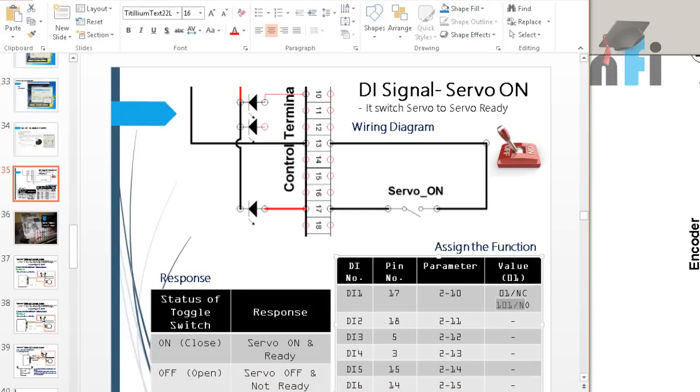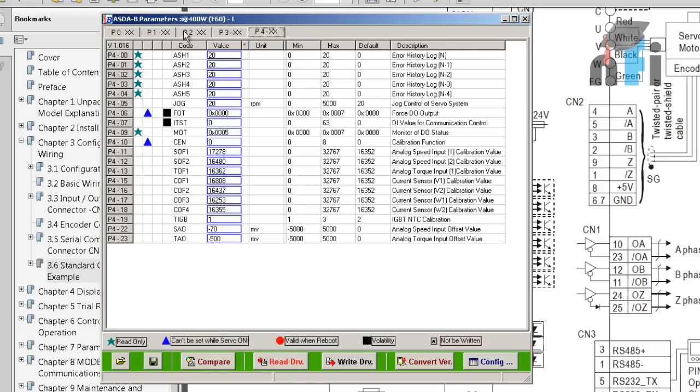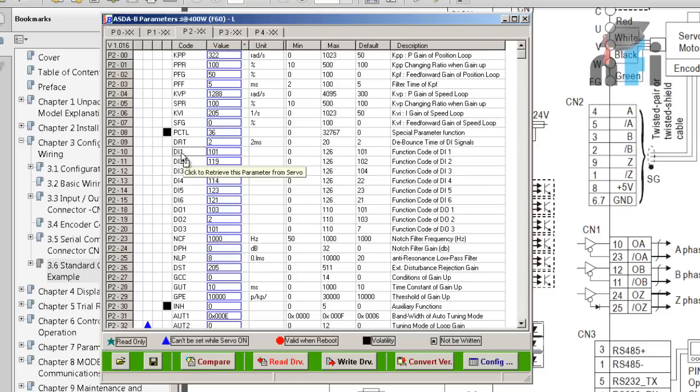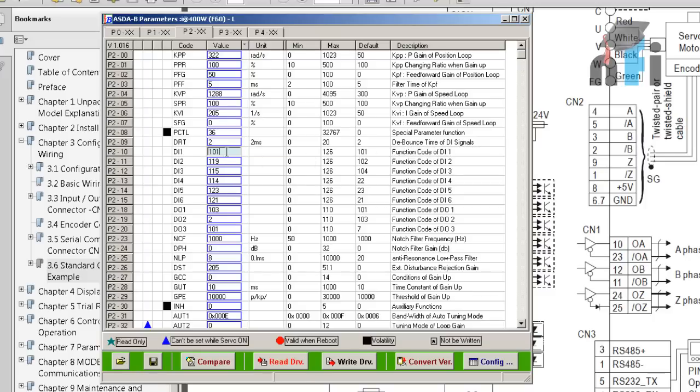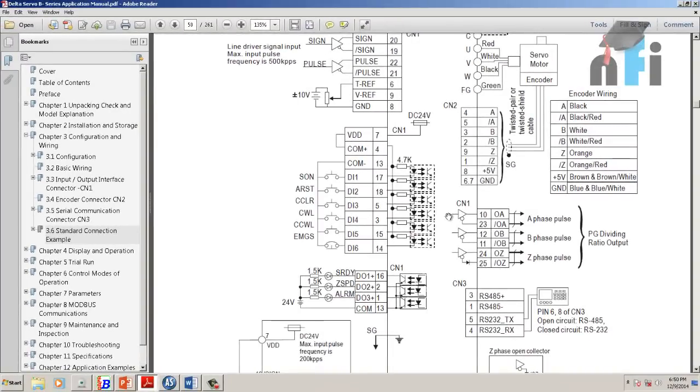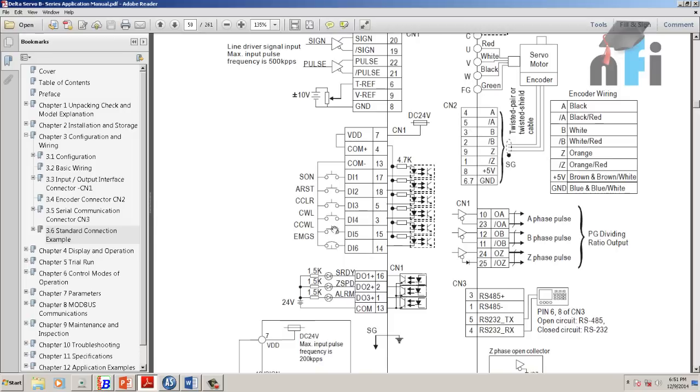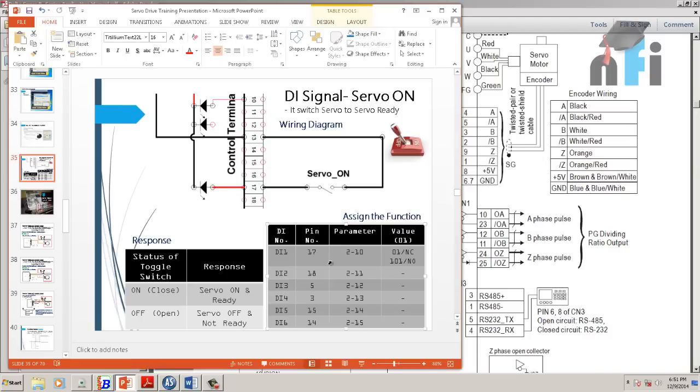So the parameter was 2-10. So I'll open up this one. This is 2-10. This is here. So this is 101. This is 101 by default. This defines the function of DI1, and why 101 defines whether the servo is on and off. This is written in the manual. If you're not using Delta servo, if you're using some other servo, they might have mentioned the function of your digital input by some codes like 101. In Delta, it defines that the servo should run, this pin should operate as servo on and off. This information has been extracted from the manual itself. It's difficult to find it otherwise, so you can use this presentation which is attached in this course to understand this function.